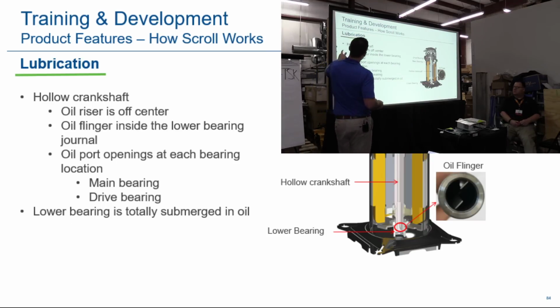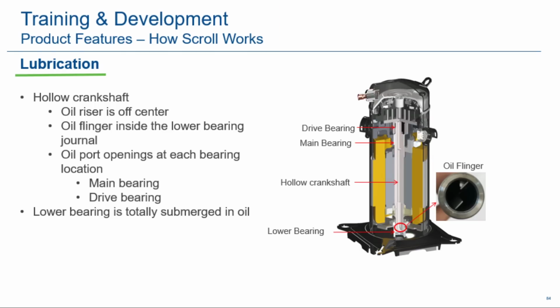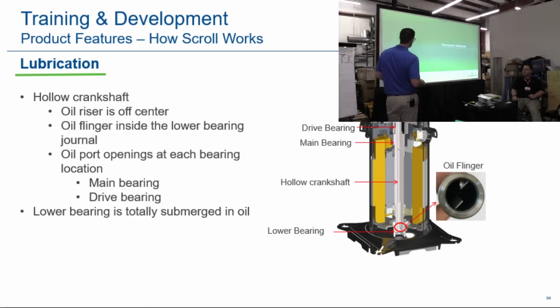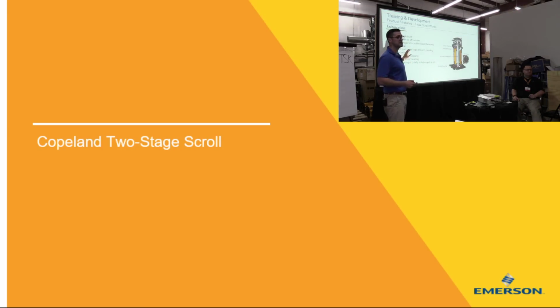How the scroll works? Well, we have a crankshaft like I talked about earlier. Down below in scrolls, it's going to be all oil. It should be all oil in there. You have a flinger oil feed. What happens here is it sucks the oil up and feeds all the bearings, right? To make sure that you have lubrication, which you need. Questions on that? Scroll design.